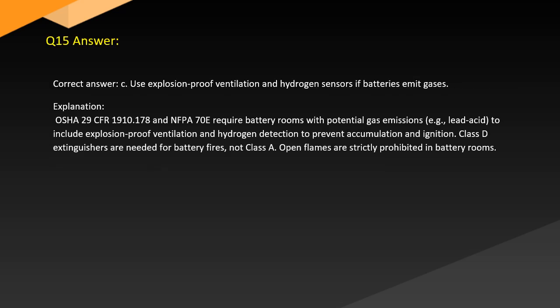Answer. Correct answer. C. Use explosion-proof ventilation and hydrogen sensors if batteries emit gases. Explanation. OSHA 29 CFR 1910.178 and NFPA 70E require battery rooms with potential gas emissions, e.g. lead acid, to include explosion-proof ventilation and hydrogen detection to prevent accumulation and ignition. Class D extinguishers are needed for battery fires, not Class A. Open flames are strictly prohibited in battery rooms.